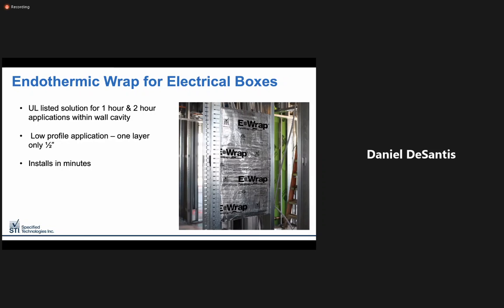Endothermic wrap is UL listed for 1 and 2 hour applications. At just half an inch thick, it doesn't require any additional accommodations for space, with generally only one layer required for these conditions. Here on the right, we have a real-world example of a recessed panel box. As you can see, the material fits neatly within the stud cavity on all sides of the box and is now 1 or 2 hour rated and just takes a few minutes to install.